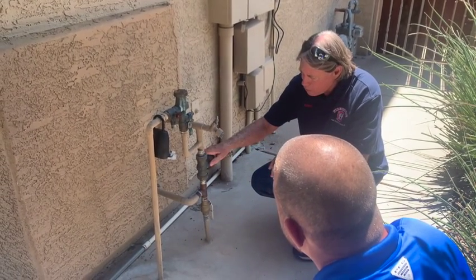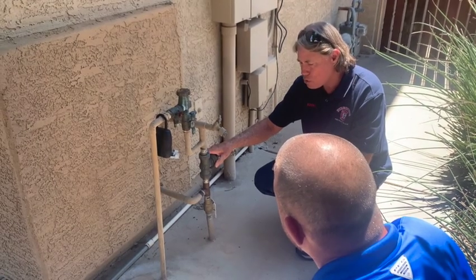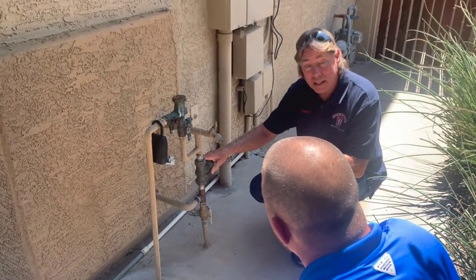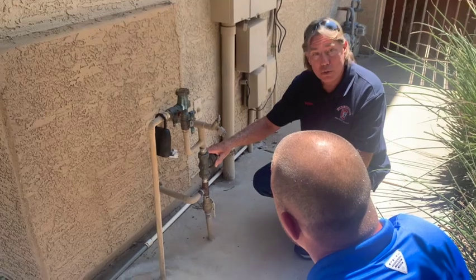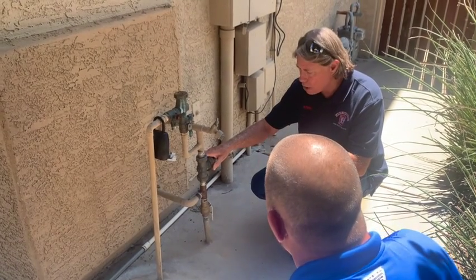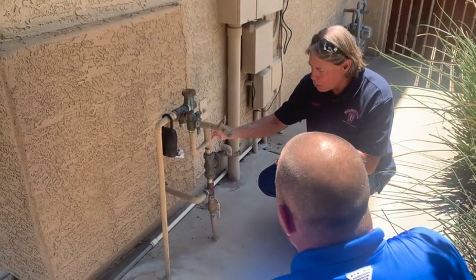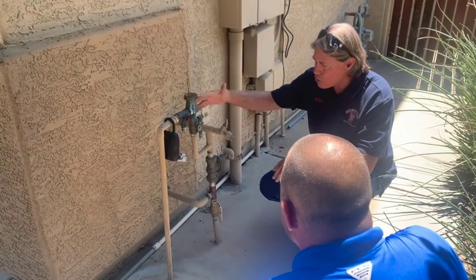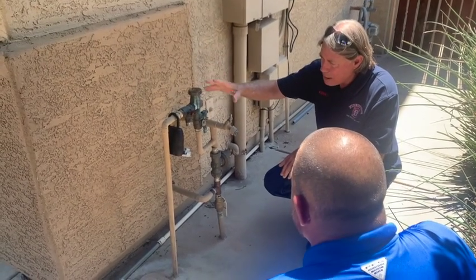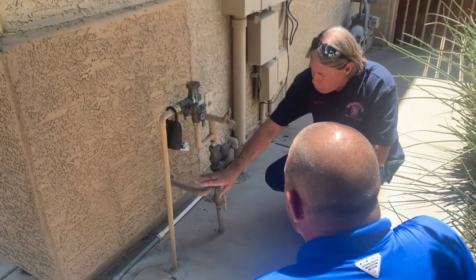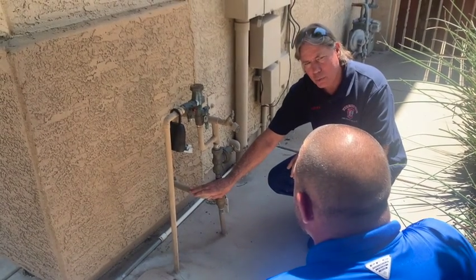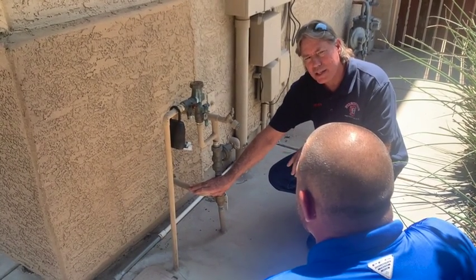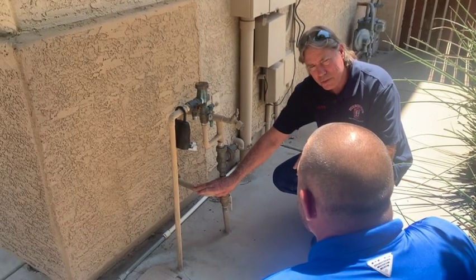This is your PRV. In this case, the acronym stands for pressure relief valve, or pressure regulating valve, or pressure reducing valve. There's two different ways that plumbers look at this. This is a plumber item. It's adjustable, so that adjusts the water pressure for the domestic and for irrigation. But we want to see street pressure. We want the most pressure, basically, that we can get for our fire sprinkler system.